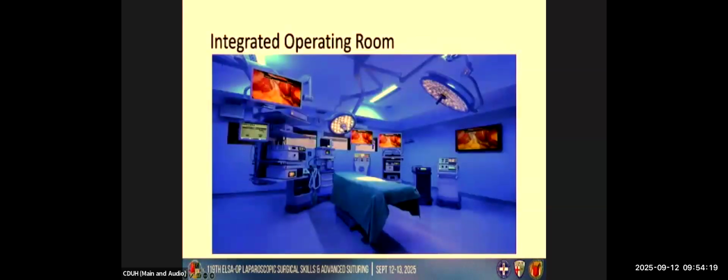This is the Endo Alpha suite we have in this institution. This is an example of an integrated operating room. Integrated ORs link the video, audio, patient data, and lights via a central console. Ceiling arms are used instead of carts to allow ease in positioning. Integration reduces door traffic, enables education and teleconferencing. Generally, it boosts efficiency and safety by centralizing control and routing.